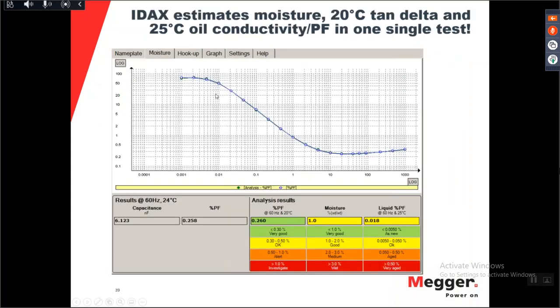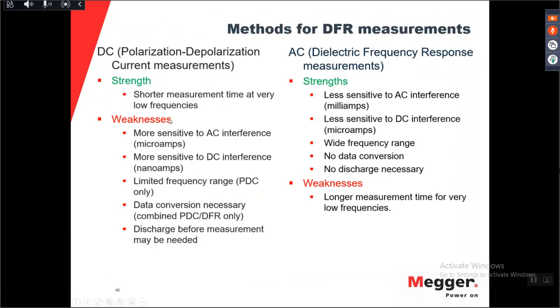So you change your time measurement to a frequency measurement by mathematical calculation, so you can use this model. So getting to these lower frequencies, it's quicker with a time domain measurement. You need less measurement time, but it has some weaknesses. Because this DC current that you're measuring is very, very low. So just a small interference current, it can be either AC or DC interference. You can see just a small nanoamp DC interference give rise to a very, very large error in your frequency conversion. This frequency conversion works very well, but if you have measured some kind of interference in your actual current, the conversion becomes very inaccurate.